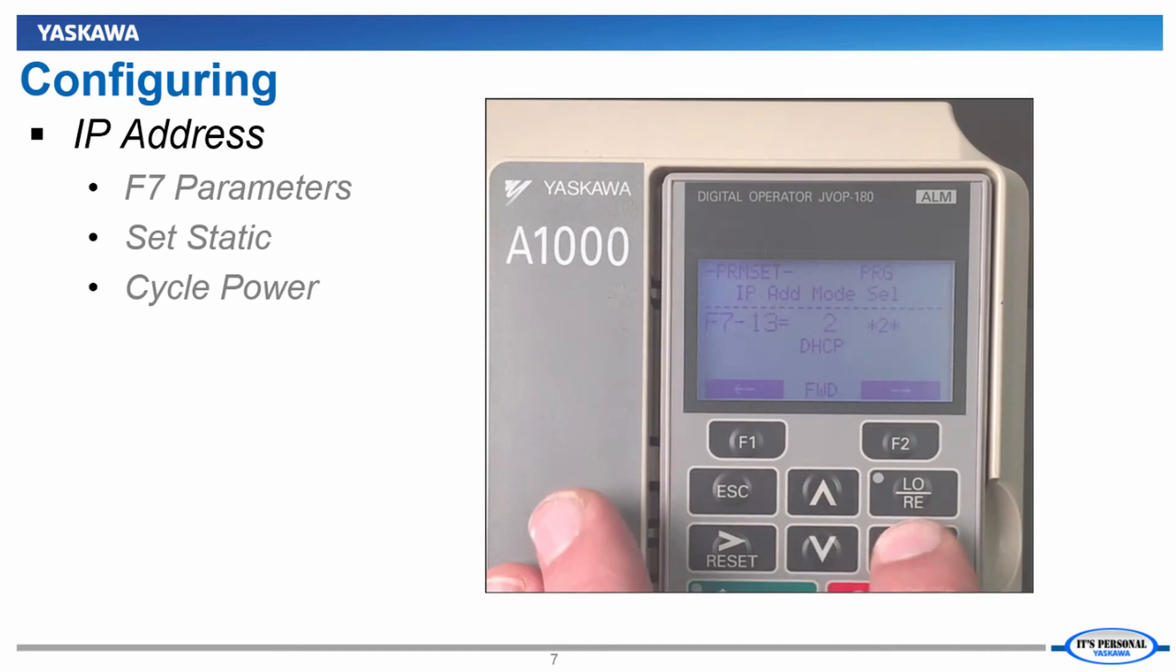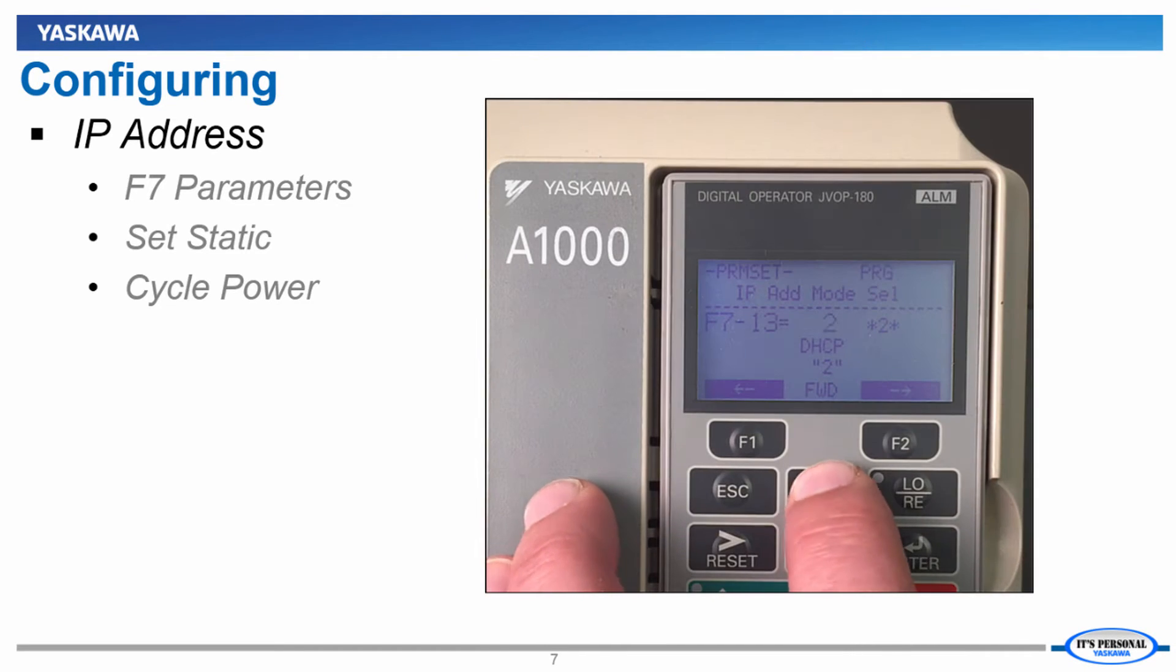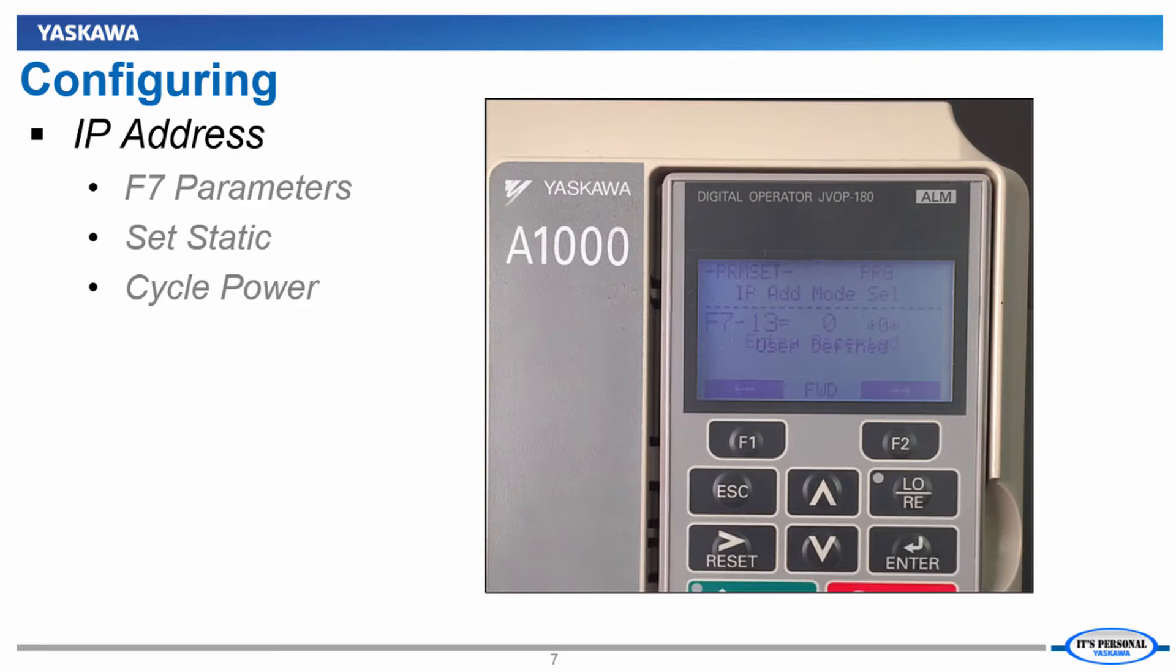Lastly, to make sure we get the programmed IP we set, change parameter F7-13 to 0, and then cycle power to the VFD.